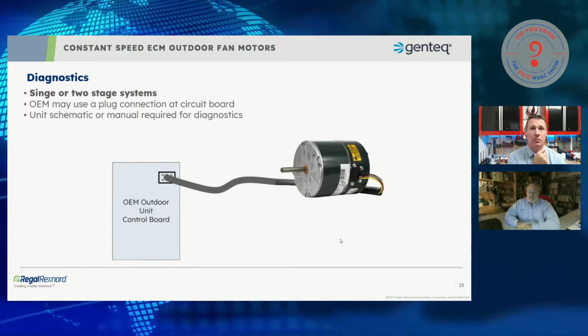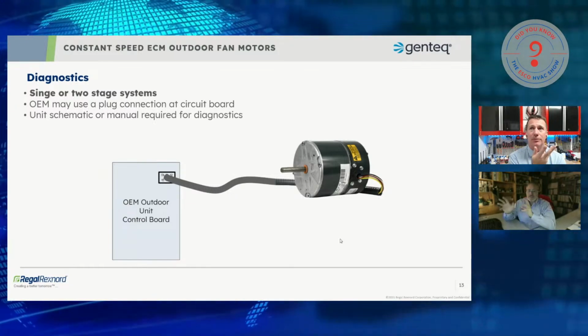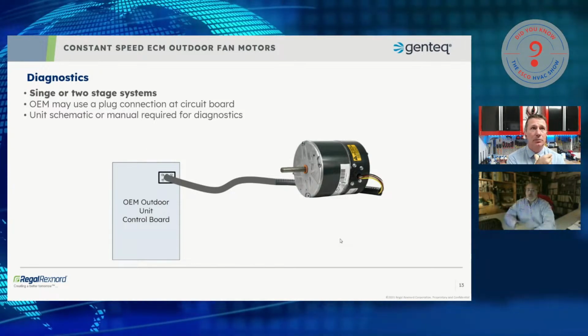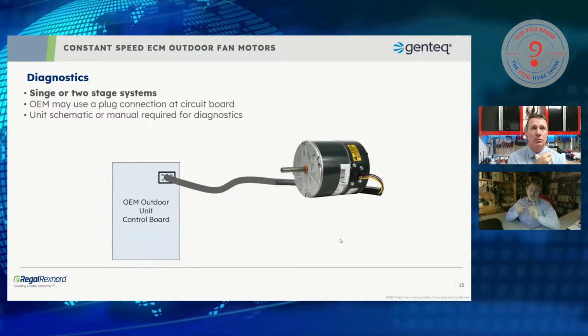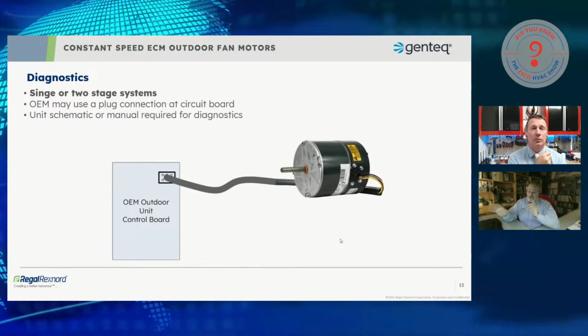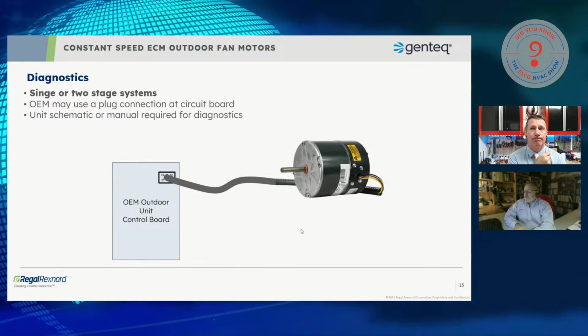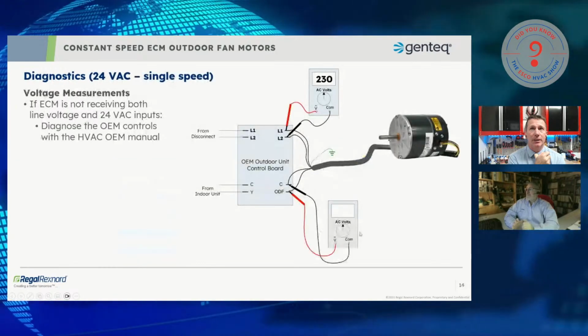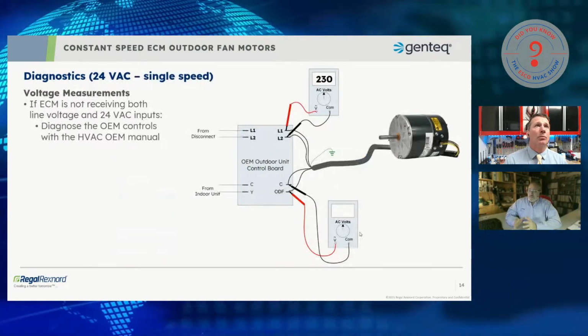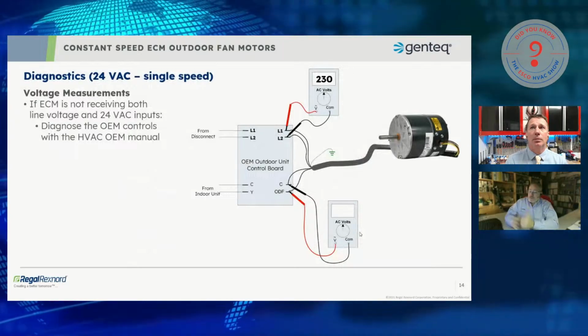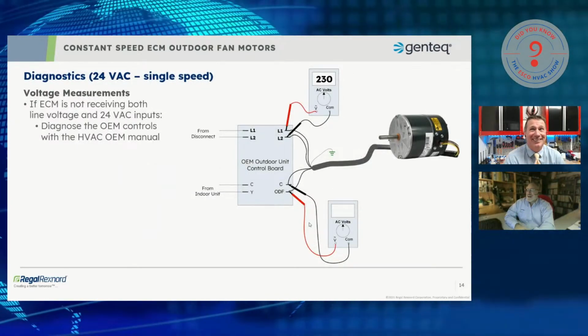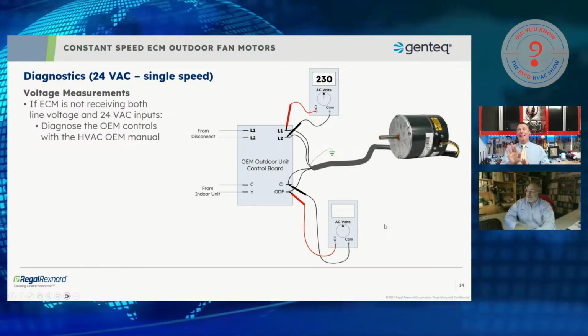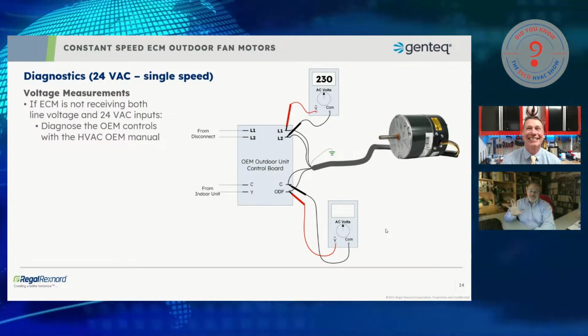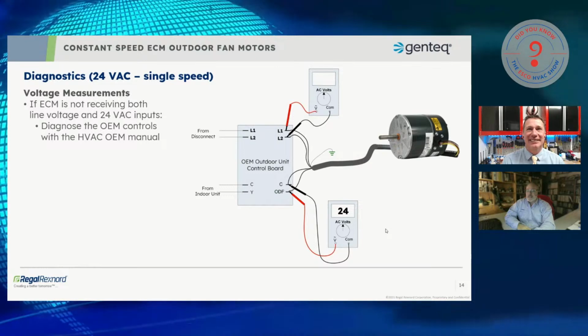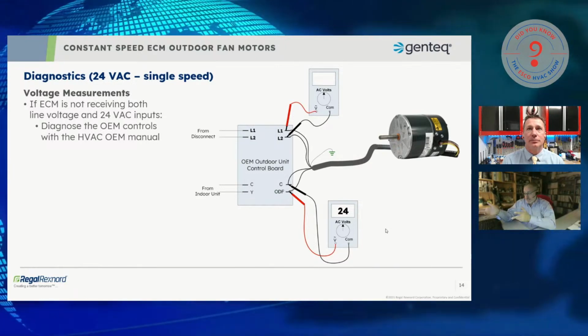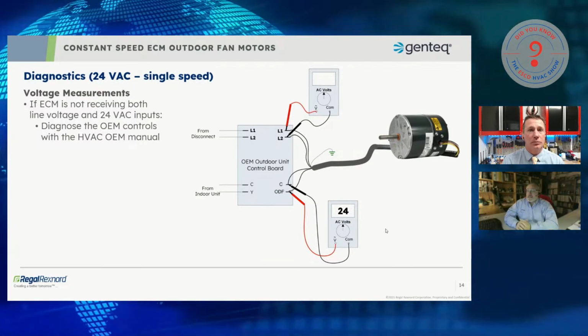I'm showing all circuit boards just because it's easier for diagram purposes, but you could see a hodgepodge of no circuit boards with contactors, or circuit boards with plugs. So I wanted to cover that quick before we dive into the diagnostics. All right. So let's start with single speed systems. You've already covered this, so I'm going to use the visual to cover the same information. You did a great job. I should just let you run this. You must have both voltages. I can't just have 230. I can't just have my 24 volts, in this case, single speed, 24-volt discrete speed. I have to have both.